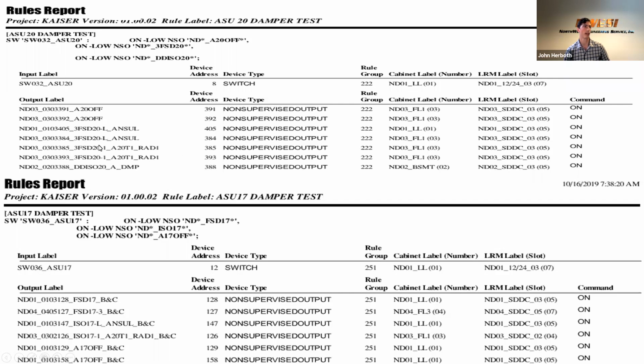This is from a Kaiser project, some of the programming that you see. And what's going to end up happening is if you can read the output labels here on the left, and the input labels, you'll see equipment type, what device type it is, and then potentially that there's FSD relays going to the Ansul system, the radiology. And so those are labeled really well, but you're not always going to come into that. And you're going to come into ones that are just labeled FSD. And that's where you have the biggest problems, is that when it's not descriptive enough to tell you what's connected to it.